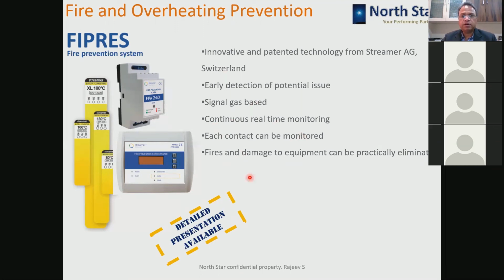So this is a very wonderful technology and solution available for non-stop continuous 24 by 7 monitoring, as against thermal imaging or thermal scanning or radiography or other such methods, where you need a person to hold that device and open the panel and do it manually, which is not that good a way of taking care of your devices, because there could be some human error, there could be some delay in monitoring, and it is person based, so the chance of risk is always there. So this is coming from our fire and overheating prevention.